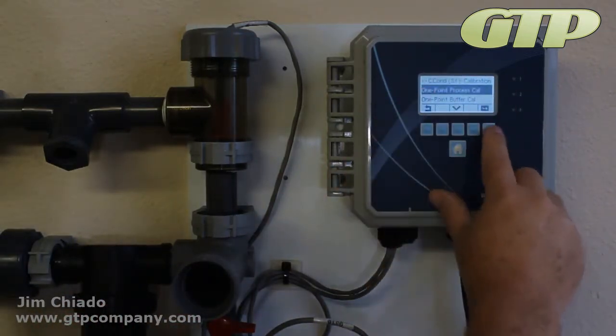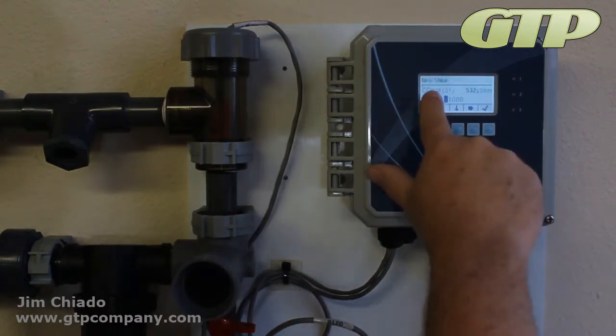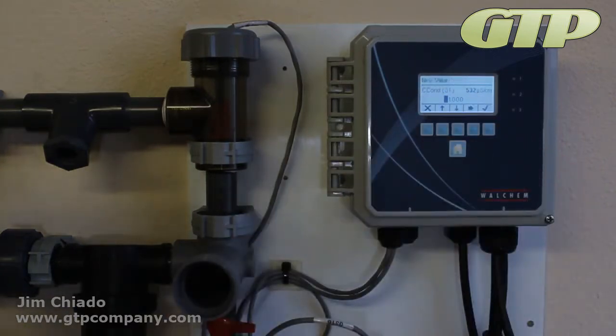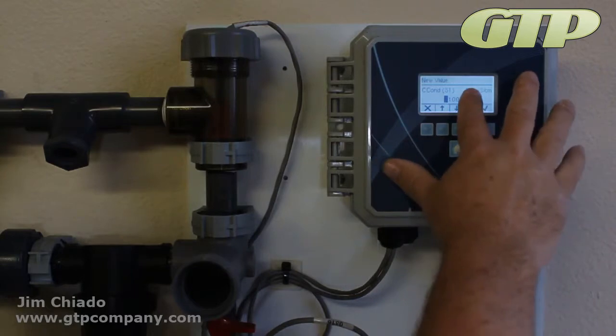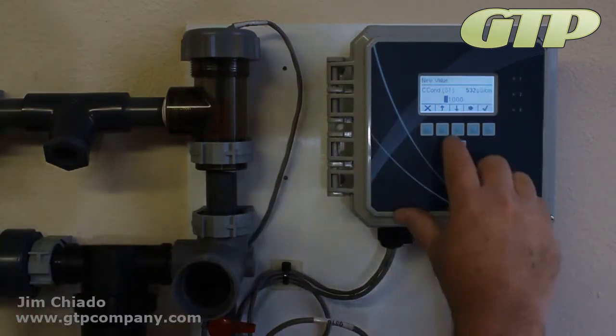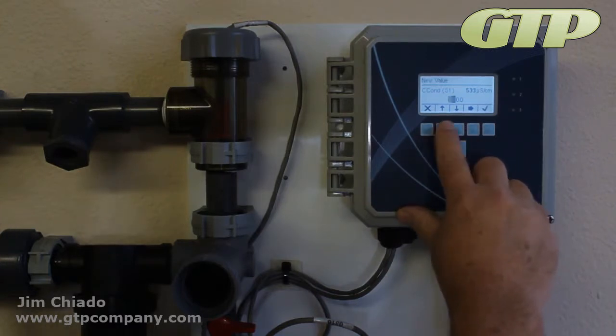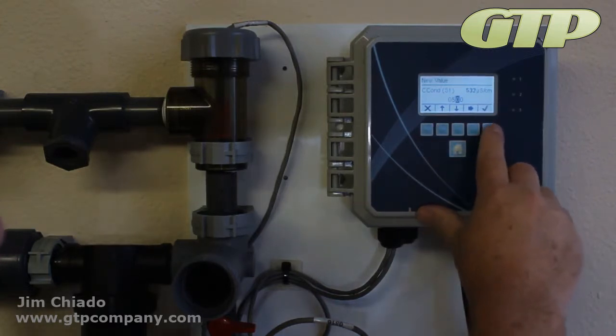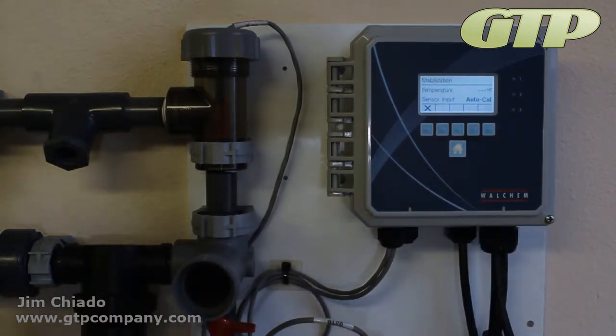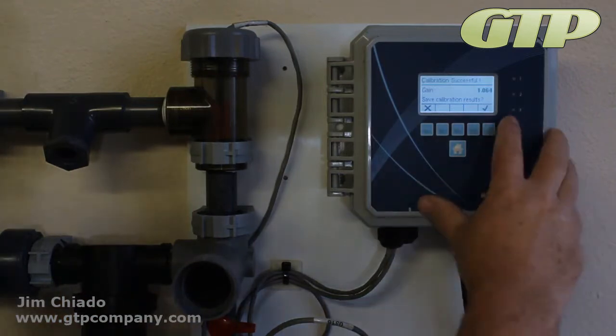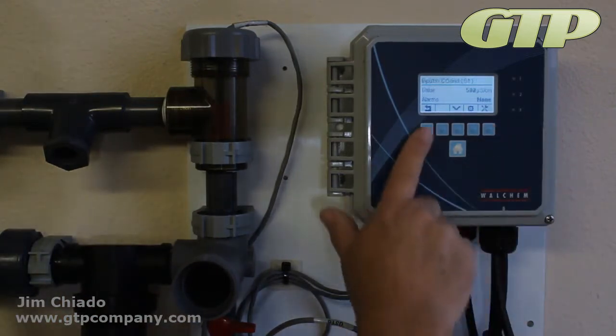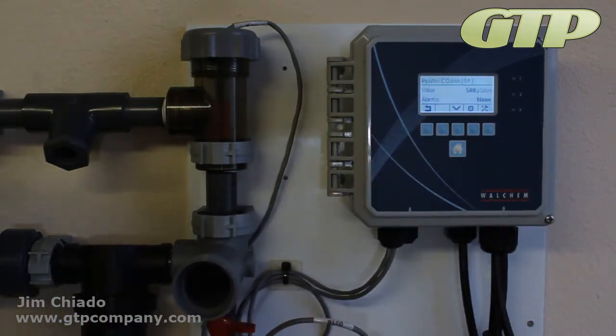We're going to go 1-point process. Right now, it thinks it's 532. Okay, so this value here is what it thinks that it is. We can make this say whatever we want. We're going to go over and say 500. We're going to hit enter. Auto cal is going to correct. It's going to come back successful. Okay, so right now you'll see it drop to 500. It thinks it's 500. We told it it's 500.